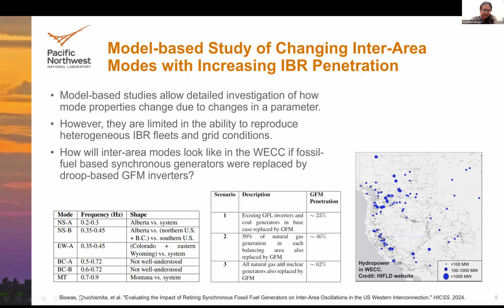On the left table, these are the known inter-area frequency ranges that we have in the Western interconnection today. I'll draw your attention to the 0.35 to 0.45 hertz mode, which is the north-south B mode, where Alberta swings against northern US plus BC, and that area also swings against the southern United States. This is a widely visible mode and of concern to system operators in the WECC today.